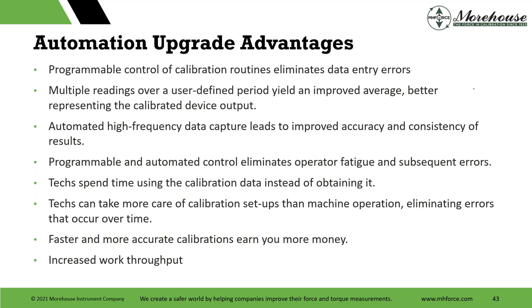Somebody can set an instrument up. Imagine this workflow. Set an instrument up, load your profile. We call them recipes around here, but load your profile for the device that you want to calibrate. There are additional safety checks. It's constantly monitoring what's being applied. In the first exercise cycle, it's going to load to 10% of that device capacity and say, is everything okay? I recommend keeping that on. It can be turned off. The technician then says, hey, my alignment's good. Everything looks good.